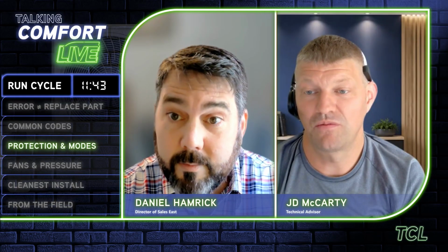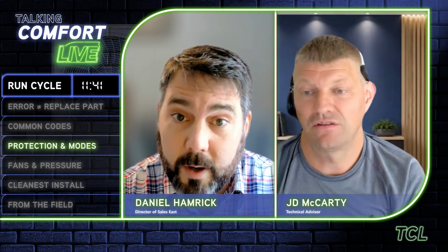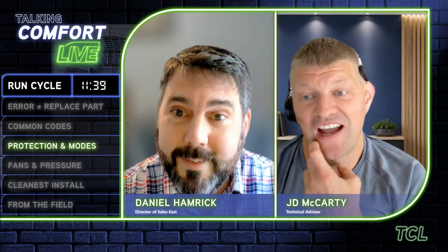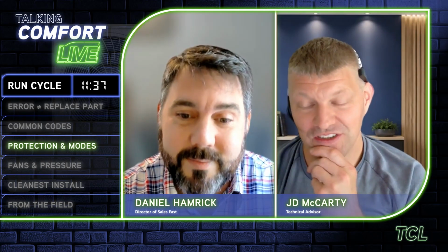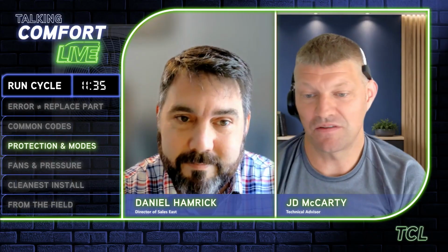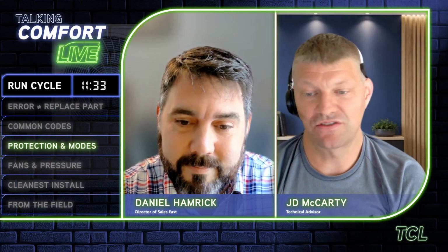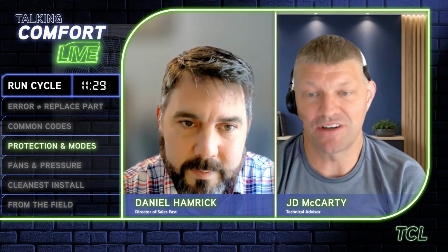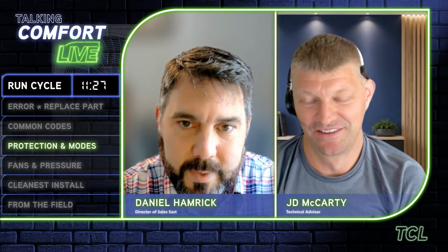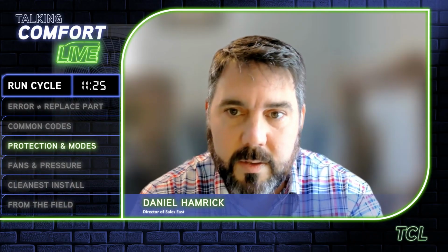Well, I know what happened when we had low airflow. They had high static, ductwork issues. Yep. As soon as I saw H4 with that unit, I knew, hey, let's go inside, get your manometer. And that's what it turned out to be most of the time.